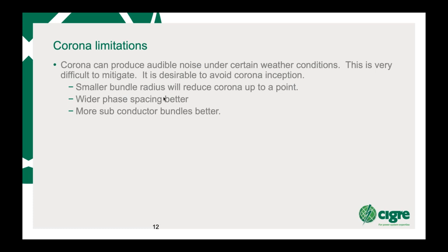Now let's see what improves corona. Smaller bundle radius will reduce corona up to a point, and then it increases again. Wider phase spacing is better and more subconductors in the bundle is better. Now there we get the wider phase spacing, which means that your L and C is now going to go in the wrong direction if you're going to meet the corona limitations. So what we need to try and do is get some kind of a balance and optimize between the two so that you meet your corona limitations as well as have optimal L and C values.